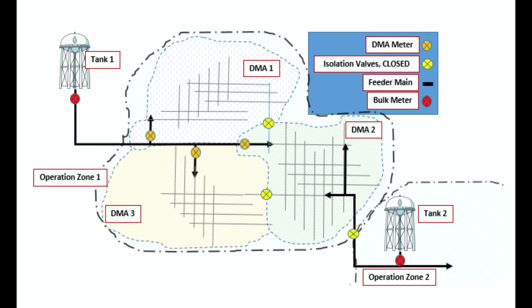DMAs are progressively chosen for providing 100% consumer metering with bulk meters at the entry of each DMA. Leakages in chosen DMAs are identified, quantified, and removed. The leakages in all DMAs are stopped so that water that would otherwise be lost is saved, which helps in increasing hours of supply. This is the basic principle of converting an intermittent system into 24x7. Each individual DMA is tackled in this way, and their combined success results in increasing water supply duration, finally converting the city's intermittent system to a 24x7 water system.